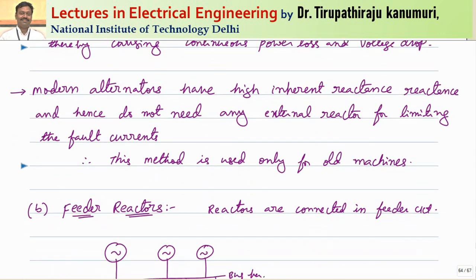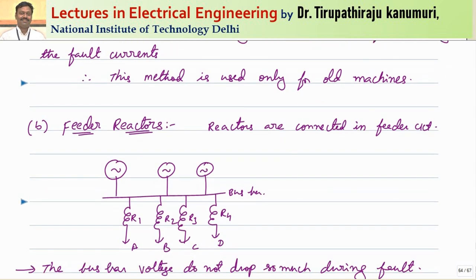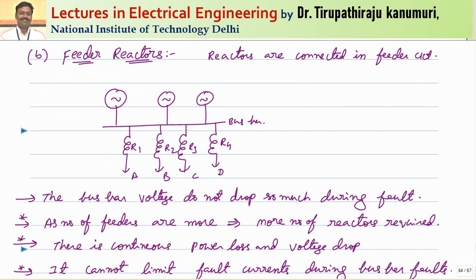This is the disadvantage of generator reactors. Modern alternators have high inherent reactance and hence do not need an external reactor for limiting fault current — this method is used only for old machines. Another option is to insert the reactors in the feeder circuits, with one reactor inserted per feeder. In this case, the problem of the common bus bar voltage dropping during a fault is avoided, because when a fault happens in one feeder, only that feeder's current is high and the voltage drops in that feeder only, leaving other feeders unaffected and the system stable.